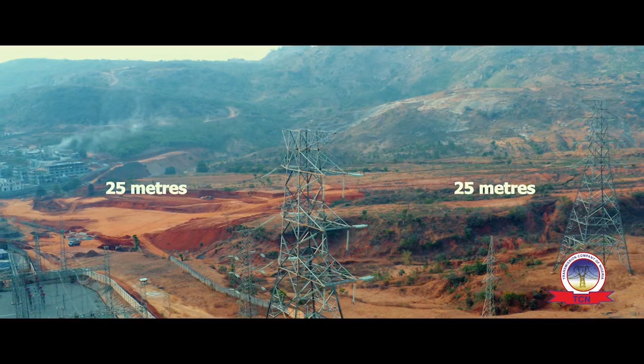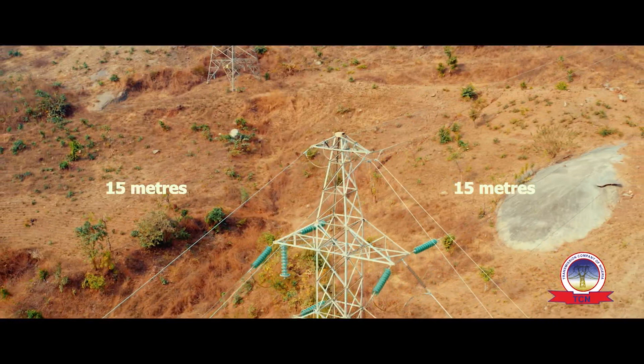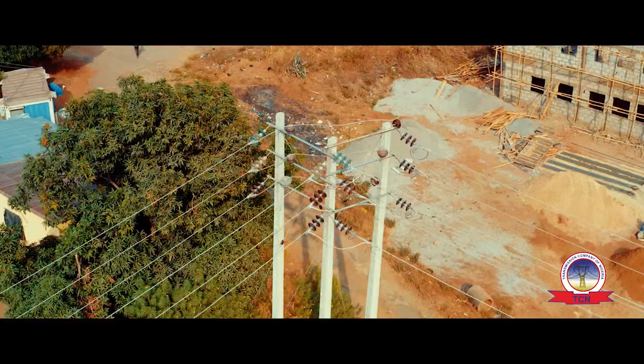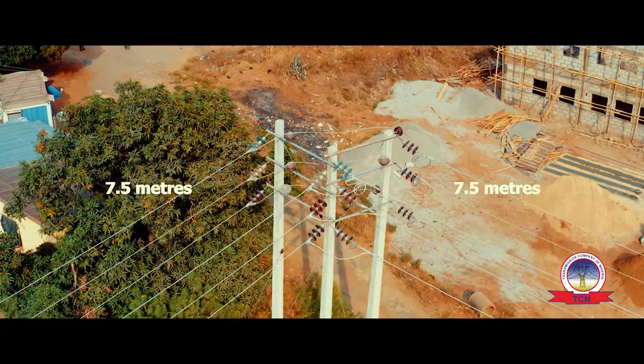Safety compliance simply means that before erecting any structure around any electricity tower or line, there are safety distances you must adhere to. These safety distances are 25 meters on both sides of the tower in the case of 330 kV, 15 meters on both sides in the case of 132 kV, and 7.5 meters on both sides in the case of 33/11 kV. These stipulated safety distance instructions are what we call right of way.